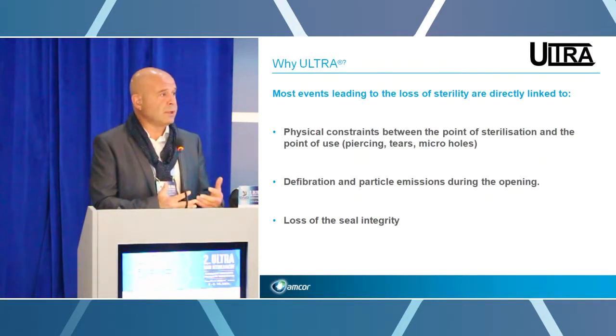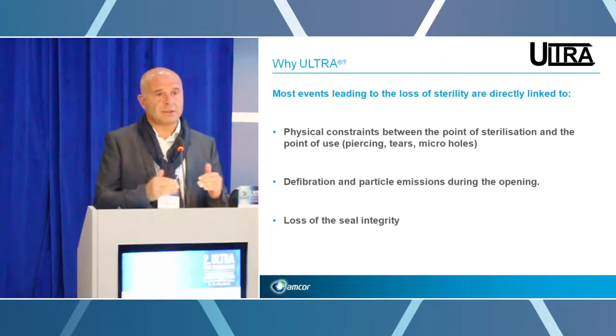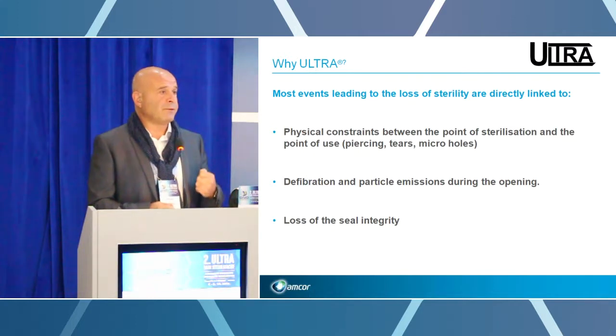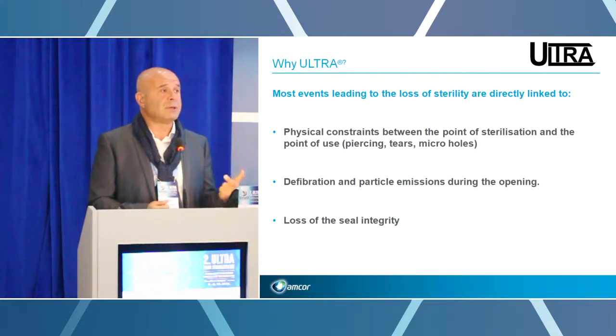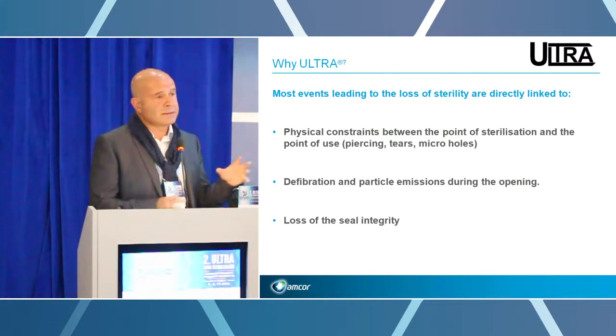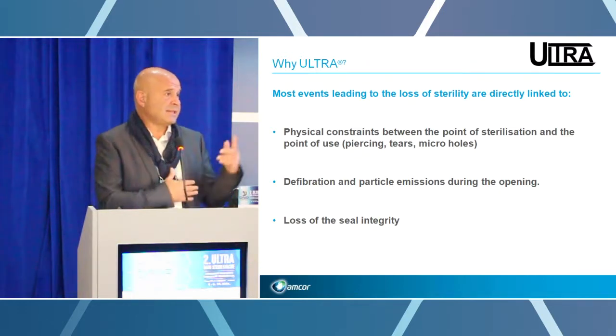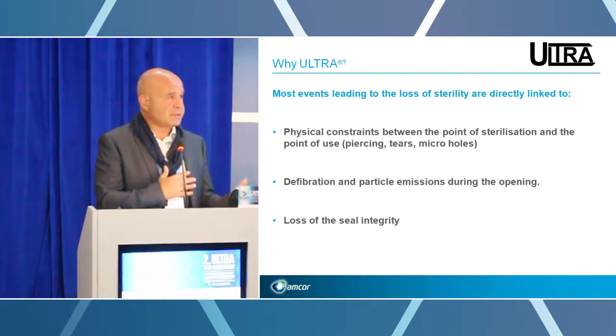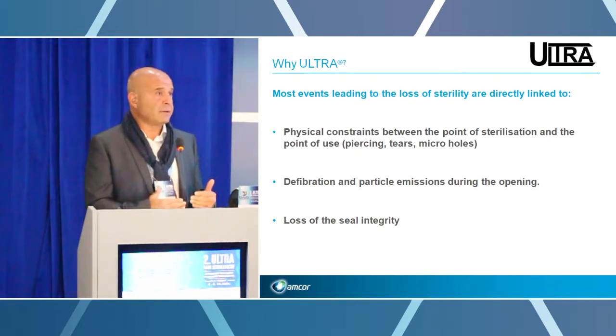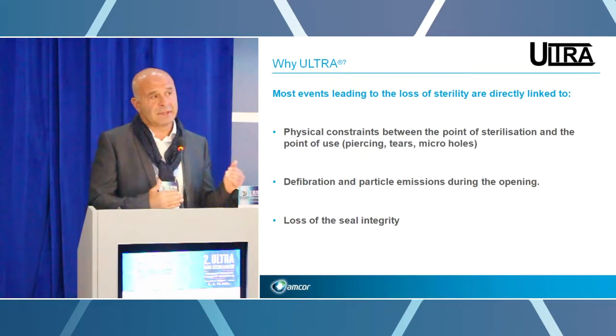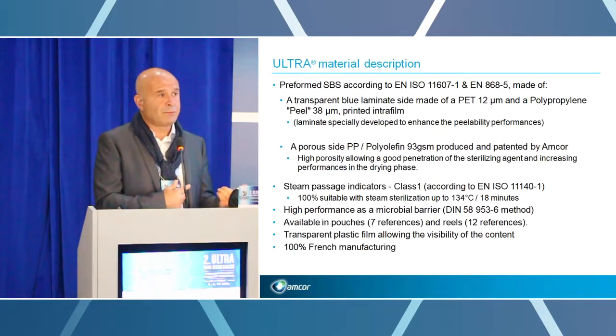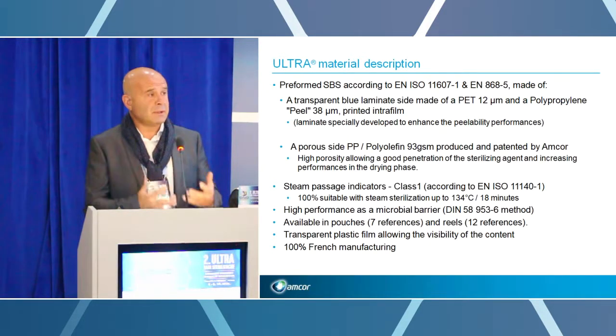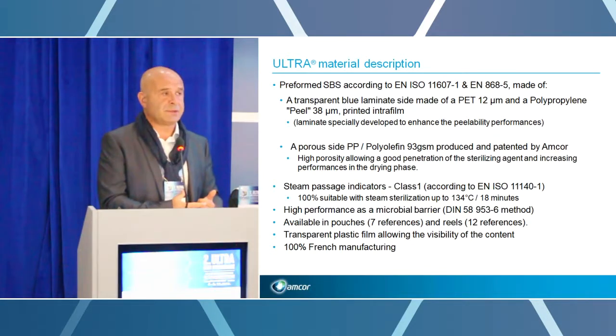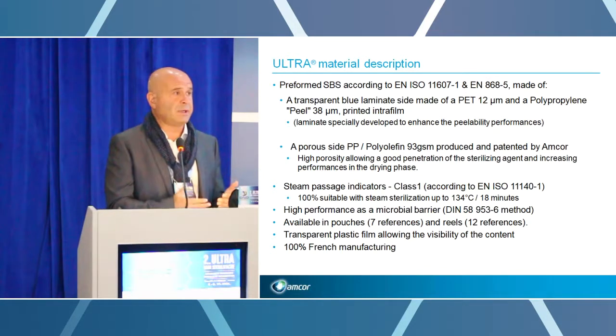We developed the film and the material. This material is a new one. It's without any fiber. It's just a synthetic fiber, with a strong resistance, with conformity to the standard, and to use in steam sterilization. Like this product, you know Tyvek. Tyvek has exactly the same characteristics in terms of resistance and conformity, but Tyvek is not possible to use in steam sterilization at 134 degrees. And it's the reason it's a new one with Ultra. It's a synthetic material, but it's possible to use in steam sterilization. This is the important innovation with this product.